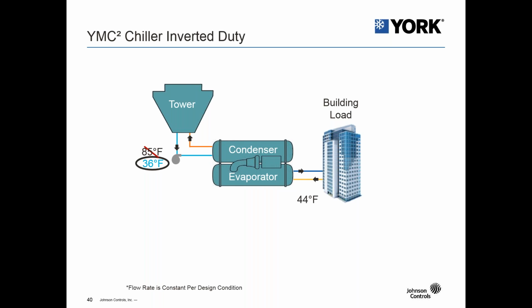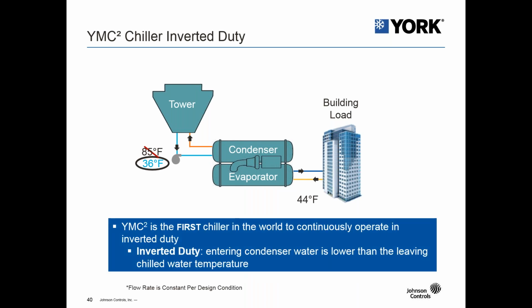But we're still able to go even further below 45 degrees. We're actually able to run inverted. So inverted means the entering condenser water temperature is less than the leaving chilled water temperature. And the YMC squared chiller is the first chiller in the world to continuously operate in an inverted duty. So in this scenario, the chiller is still operating the same way it would at 85-degree entering condenser water temperature or 50-degree entering condenser water temperature. It's still providing mechanical cooling. We're still having the refrigerant complete the refrigeration cycle while running the compressor.